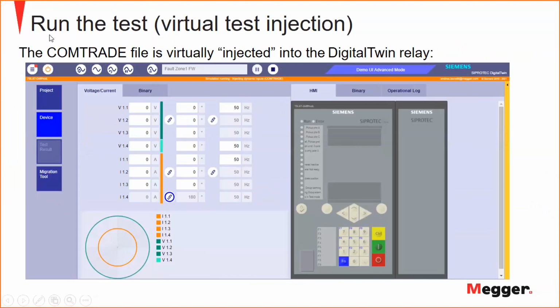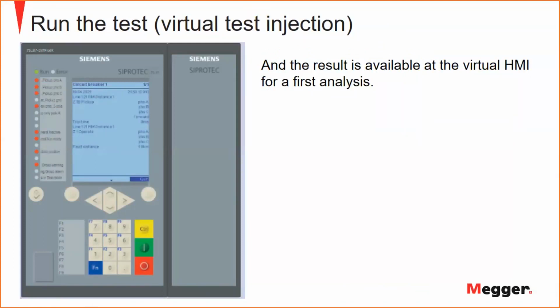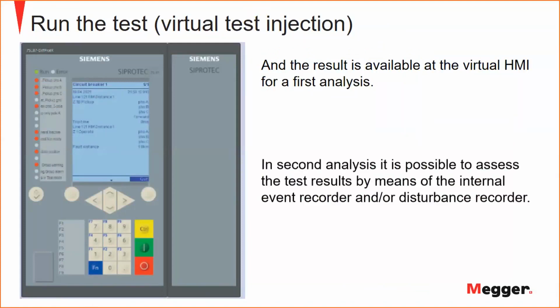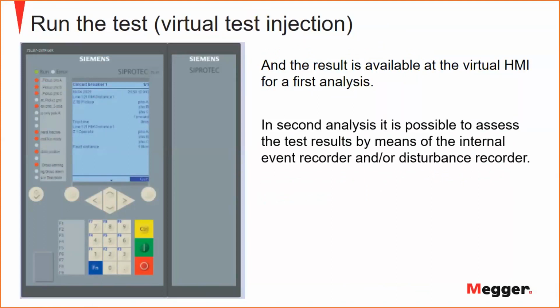Then you click on this button, start a simulation of the digital twin. You go here and select, it's a little bit difficult to show it on PowerPoint, you select the COMTRADE file you played out, and as a result it is available at the virtual HMI for the first analysis. You see trip, fault, distance to fault, whatever you would see on a real relay. In the second analysis, it is possible to assess the test results by using the event recorder and the disturbance recorder. So you connect to this relay with DIGSI, you upload the disturbance recorder, you can measure the trip time, you can see if it tripped in the correct way, if it behaved correctly, etc.